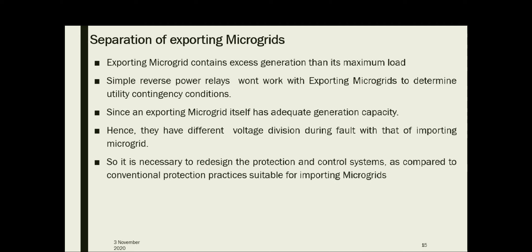Implementing an exporting microgrid would require a major redesign of the protection and control systems compared to conventional protection practices, which are suitable for importing microgrids. When designing a protective system for an exporting microgrid, we cannot simply adapt the same approach used for an importing microgrid.